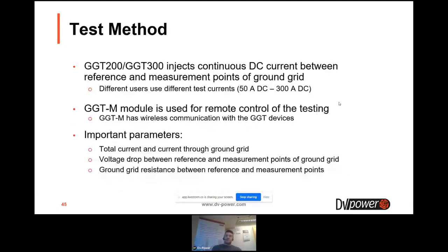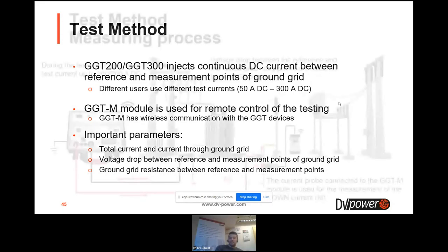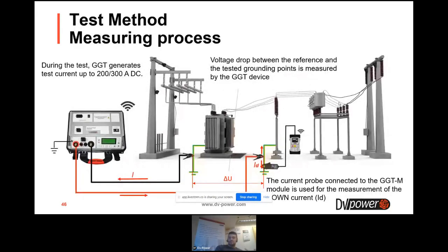So I will just show how the test is done. Usually it's good to have a remote control module because the operator is at a very high distance from the device. So this is the test setup. You will have one short test lead, which is the black cable, connected to the reference grounding point in the substation.